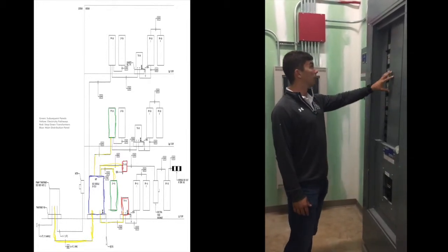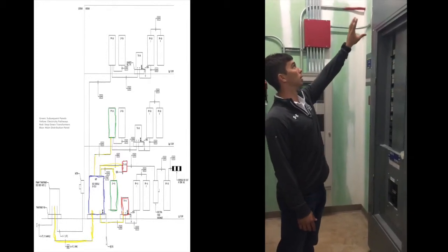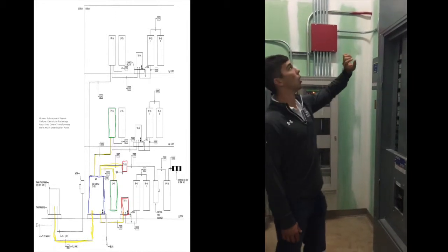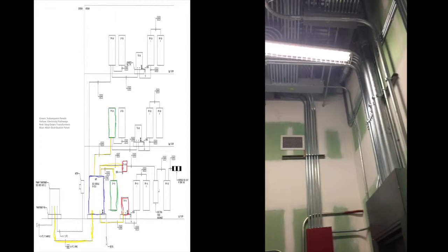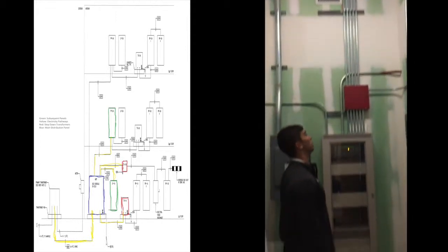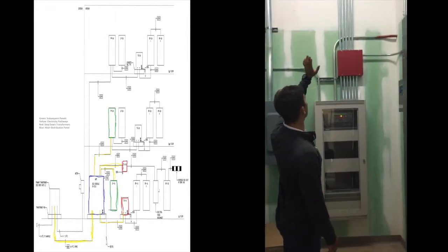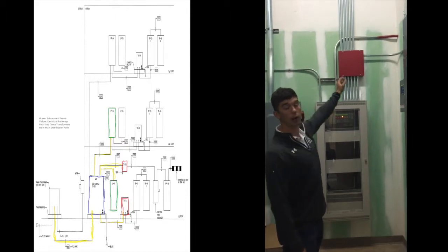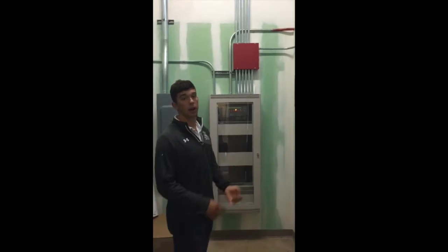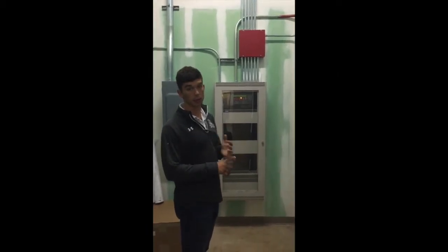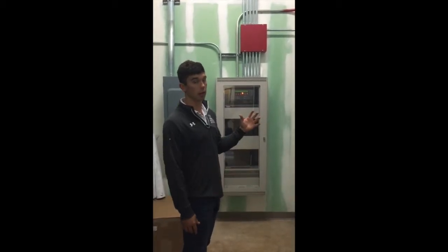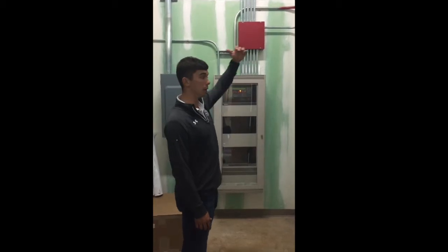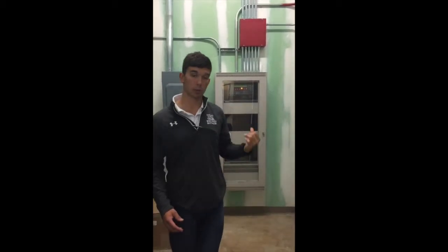The circuits leaving this main distribution panel that are 480 volts are then going up through conduits which should already be there, which can be hung as soon as the wall has any kind of finish on it, to the main 480 volt electrical equipment. At that point, it has a disconnect switch added to it and a control panel, or some kind of control panel, and the 480 volts can either go immediately into the equipment, or it can go into a subsequent panel purely devoted to running that high voltage equipment.